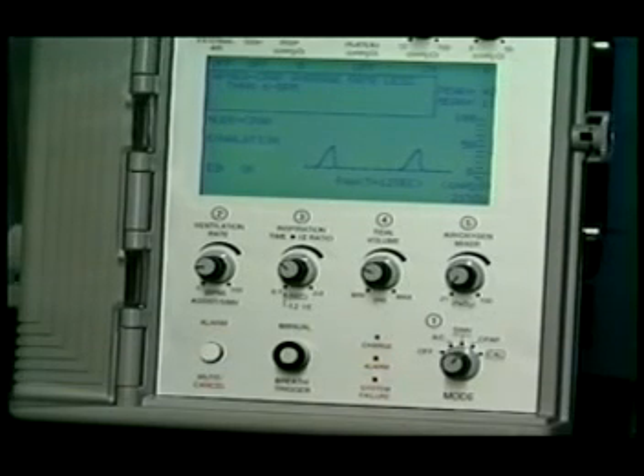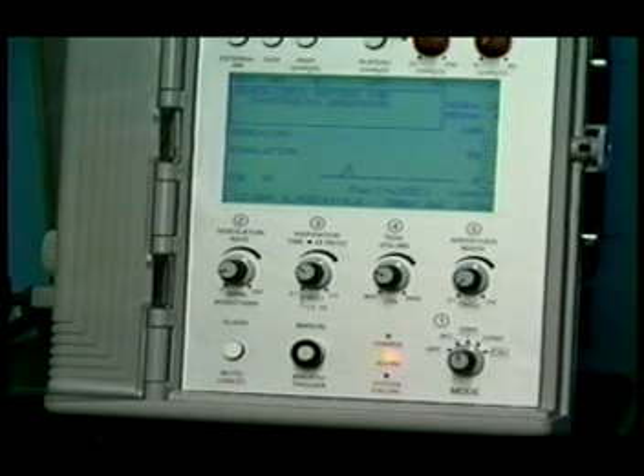When apnea occurs in CPAP, default values for ventilation rate, inspiratory time, gas flow, and maximum peak inspiratory pressure are invoked. Default values protect the patient because the ventilator cannot tell whether the patient is an adult, child, or infant. When apnea occurs in the assist control or SIMV modes, ventilator-generated breaths equal the current inspiratory time and tidal volume control values set by the operator.